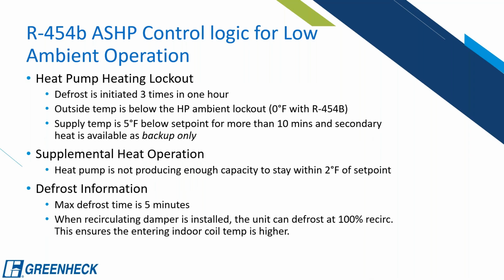In regards to the heat pump locking out, there's only 3 conditions that would really cause that. 1, if defrost is initiated 3 times in 1 hour. 2, if the outside temp is below the heat pump ambient lockout of 0 degrees. And then 3, if the supply temp is 5 degrees below the set point for more than 10 minutes, and if the secondary heat is available as backup only.